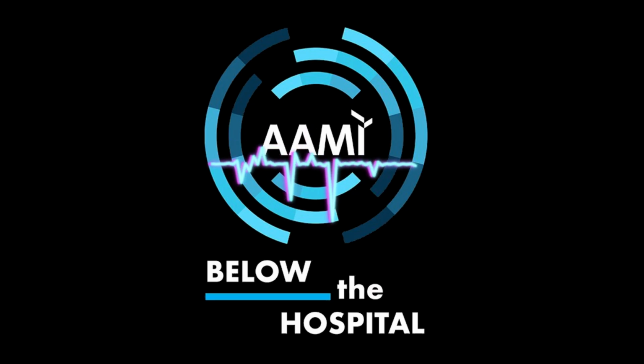One of the things that has come up is that smaller hospitals oftentimes have budgetary constraints. They may not be able to afford the full range of technologies that a large acute care facility can. And in that case, I would argue that an ethylene oxide sterilizer is a good general purpose sterilizer. Again, it's not as fast as the hydrogen peroxide systems, but you can put everything into it.